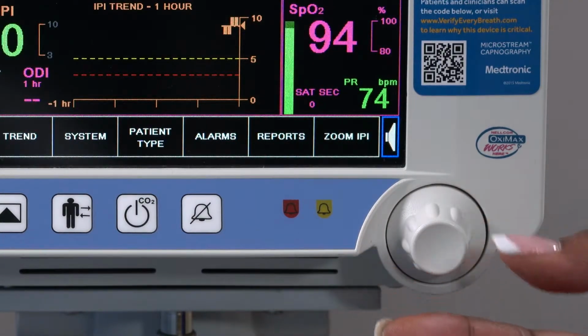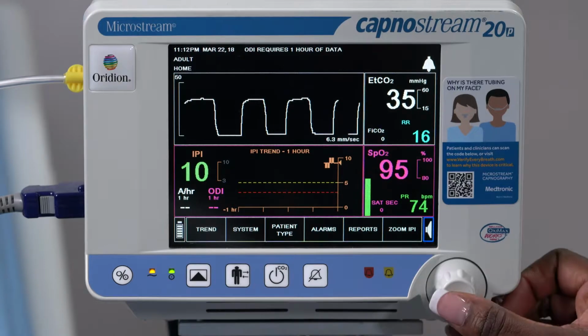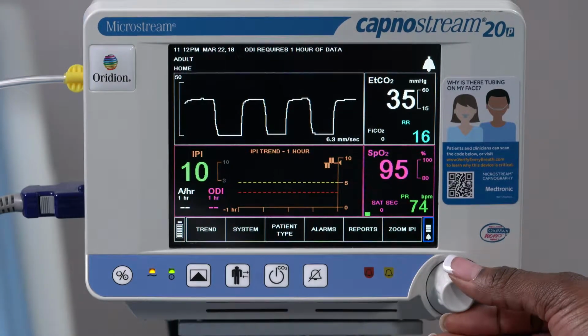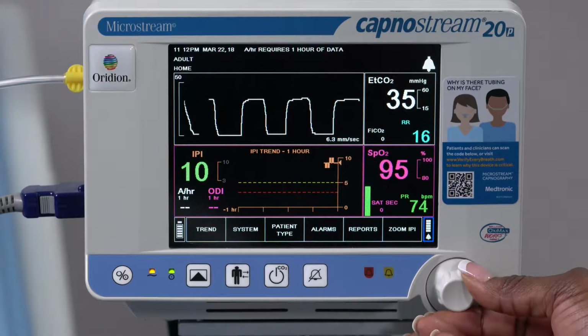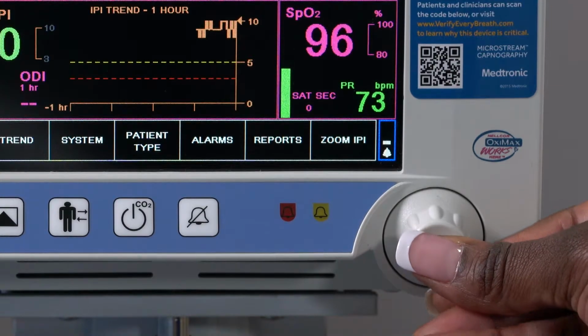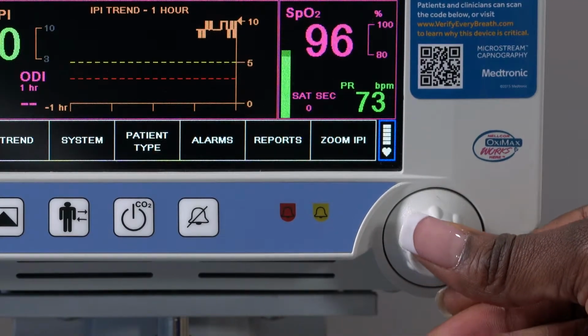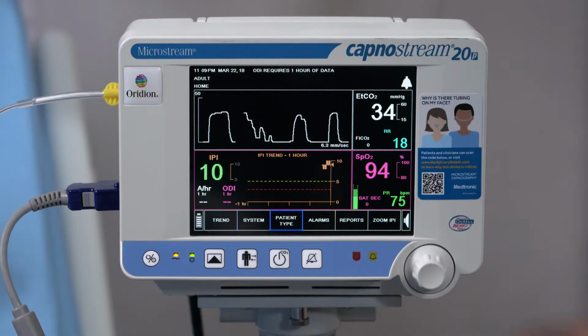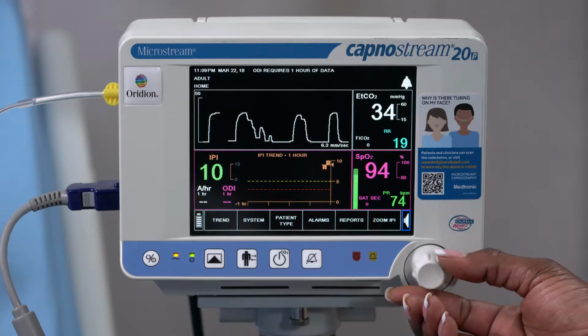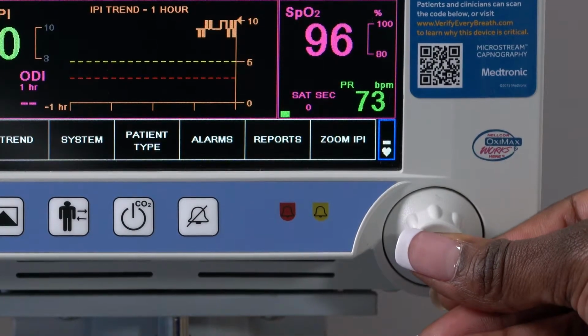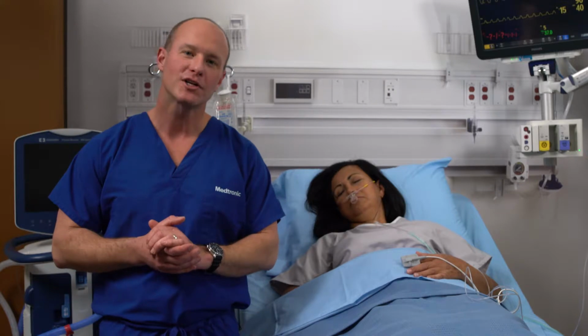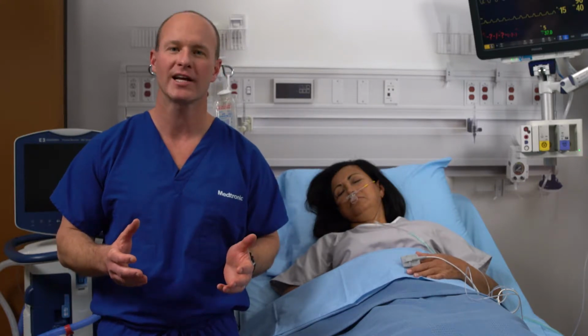Use the control knob to scroll to the speaker icon. Click the control knob once to select the alarm volume control. Turn the control knob to raise or lower the volume. Click the knob twice to set the new volume level. Use the control knob to select the speaker icon and click twice to select the pulse tone volume setting. The monitor is plug and play, so you'll be up and running in no time.